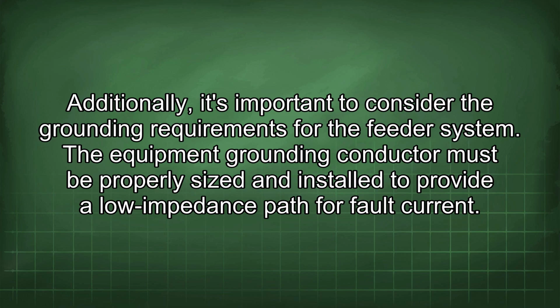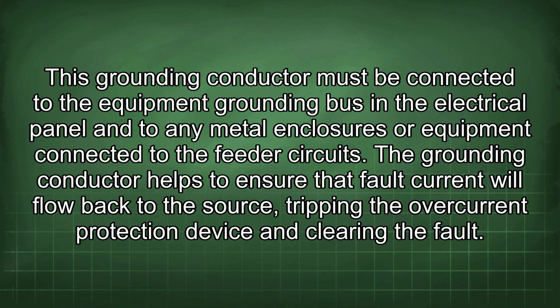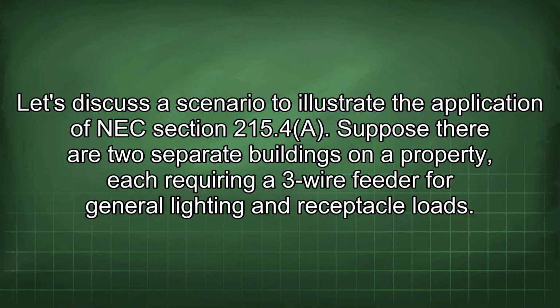Additionally, it's important to consider the grounding requirements for the feeder system. The equipment grounding conductor must be properly sized and installed to provide a low impedance path for fault current. This grounding conductor must be connected to the equipment grounding bus in the electrical panel and to any metal enclosures or equipment connected to the feeder circuits. The grounding conductor helps to ensure that fault current will flow back to the source, tripping the overcurrent protection device and clearing the fault. Let's discuss a scenario to illustrate the application of NEC section 215.4a.